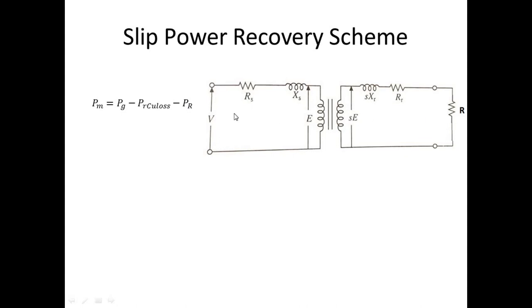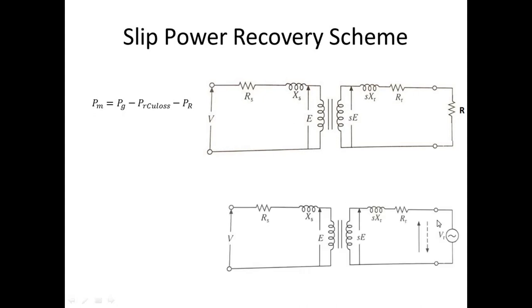The power lost across the external resistance is wasted — that is the disadvantage of rotor resistance control. In the slip power recovery scheme, instead of dissipating this power in a resistance, we connect a voltage source here. This power can then be transferred to the supply line or a battery, so that wasted power is recovered and utilized.